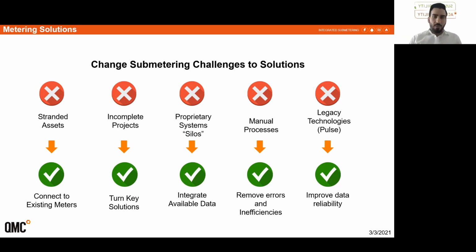So if I may add, a sample of what we have come across at QMC a couple of years ago with a proprietary system with one of the universities with about 80 or so buildings in Toronto. They were really dissatisfied and fed up with the metering provider within the campus, and they were trying to integrate the data within the BMS systems on campus, and they found out that that metering provider would charge them some really hefty amounts in order to give them that access. And after doing a cost analysis, they ended up replacing all meters throughout all 80 buildings within the campus. That just goes to show it is very important to have a non-proprietary system with open communication protocols to be able to give access to different stakeholders as the direction for the property changes.